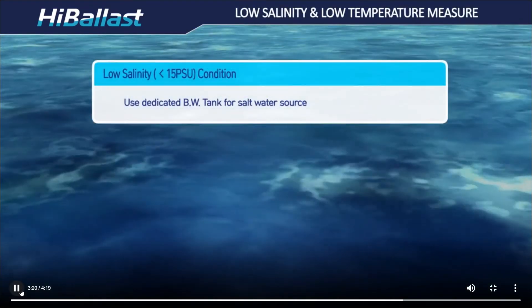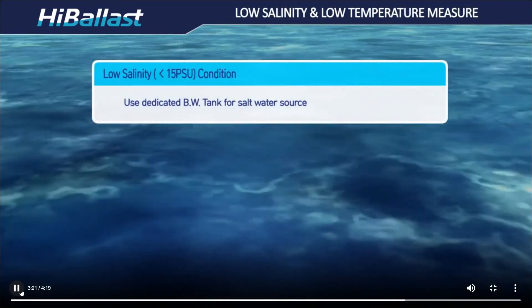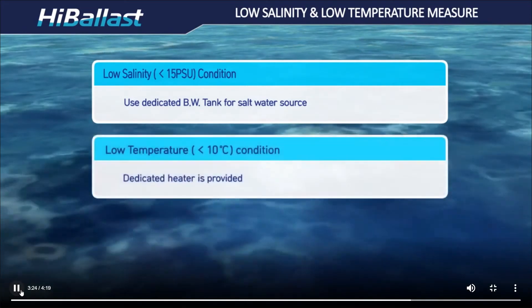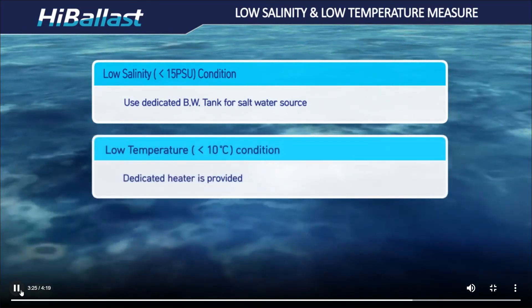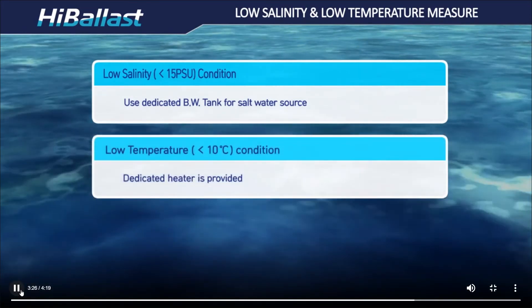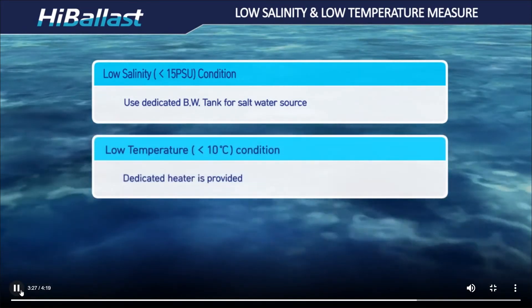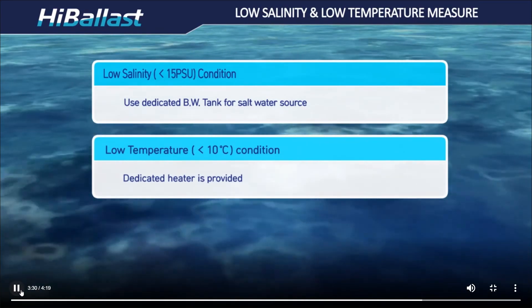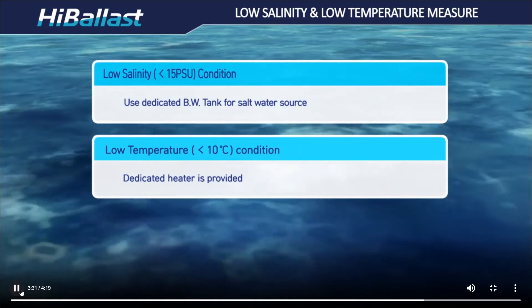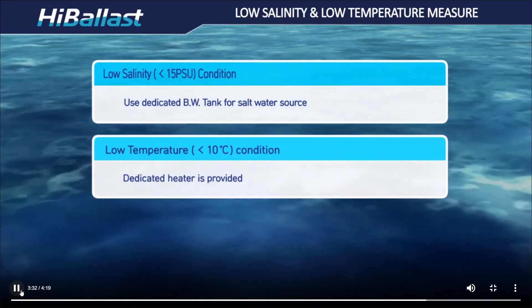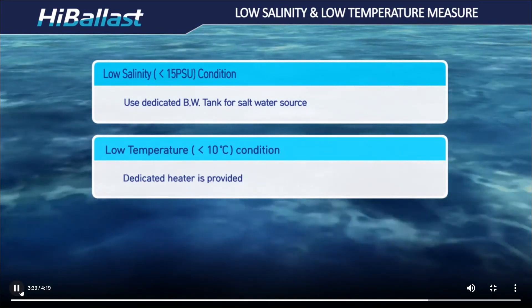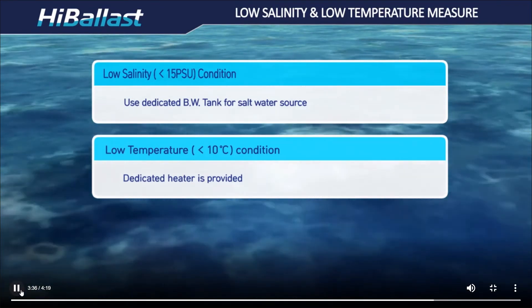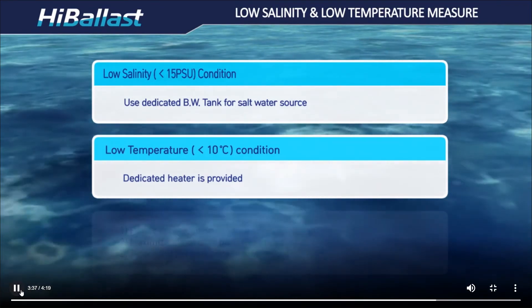At low salinity water, in order to maintain good performance, one of the ballast tanks or a dedicated tank is used as a saltwater source. In case the temperature of seawater is too low, a dedicated heater warms up seawater to the optimum level.